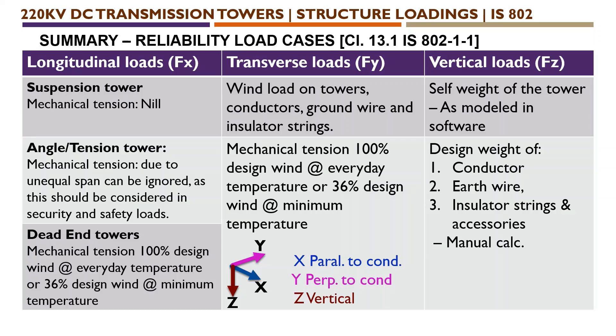For dead end towers, the longitudinal forces we need to consider are: 100% designed wind at everyday temperature, or 36% designed wind at minimum temperature. These are the three parameters under which we need to consider the longitudinal loads for reliability load cases.